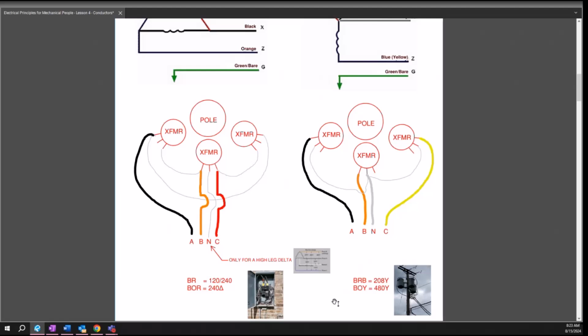And I just needed a couple of receptacles. It didn't make sense to install 208Y because that would add more load and cost the client more money for the install — it would just overall cost more. If I only need a couple of receptacles, like 10, 15 maybe, pull that neutral on a 240 Delta and be done with it. It's much easier, cheaper, because as voltage goes up, current goes down, so if I have less current flowing through there, my conductors don't have to be as big.